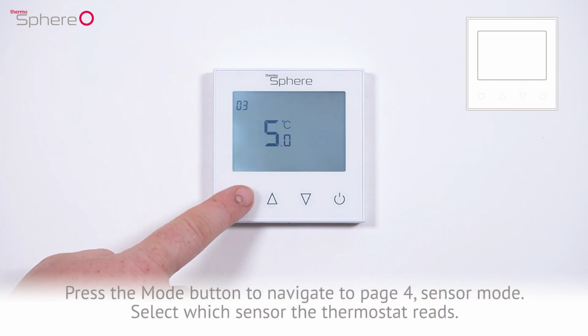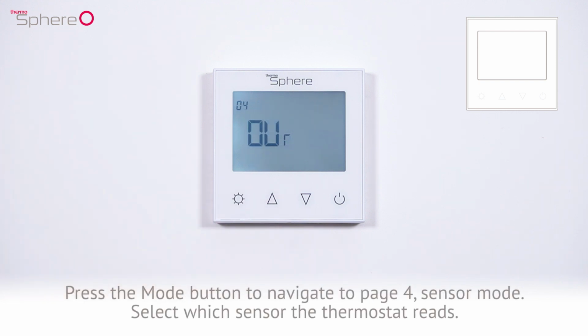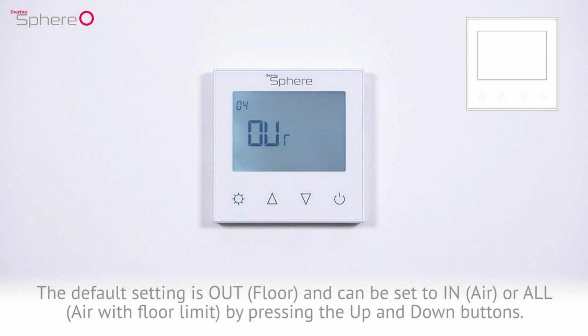Press the mode button to navigate to page 4, sensor mode. This is where you can select which sensor the thermostat reads. The default setting is out, or floor sensor, and can be set to in, which is air sensing, or all, air with floor limit, by pressing the up and down buttons.